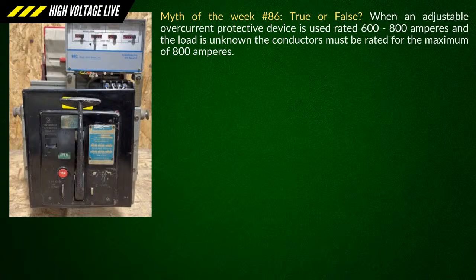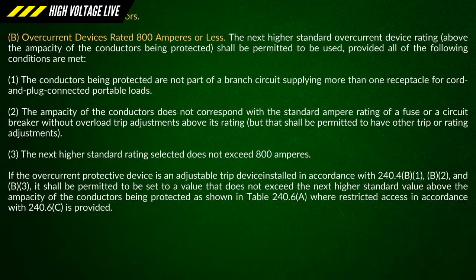Now, I want to point something out here. Let's just do a hypothetical, because we're going to get into this in a little bit, and I'm going to show where this isn't correct. He says, what if I'm supplying my loads, and I size my conductors, and my conductors come up with 620 amps? Your conductors could be 620 amps, but you're also protecting the load. Well, let's say the load was 588 amps. So you automatically know you're going to need a 600 amp overcurrent protection device, correct? Because you're protecting the load.